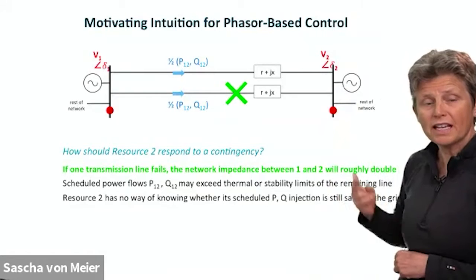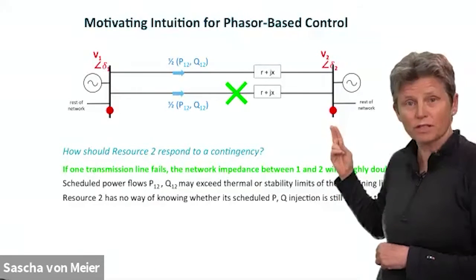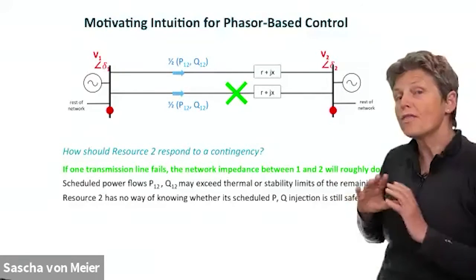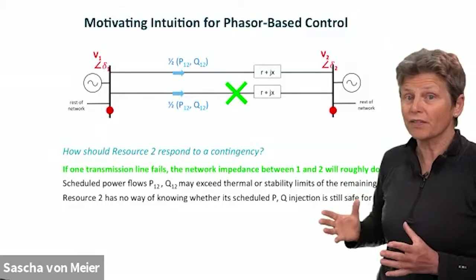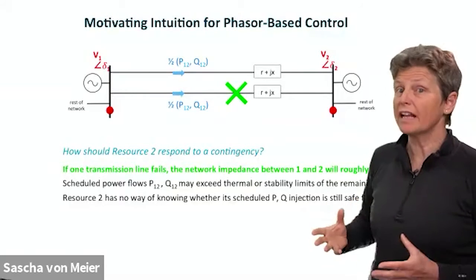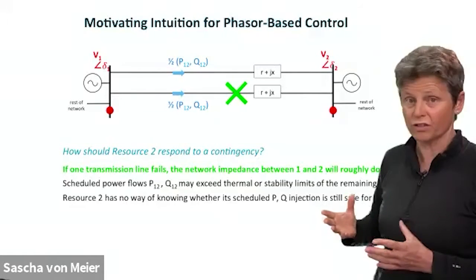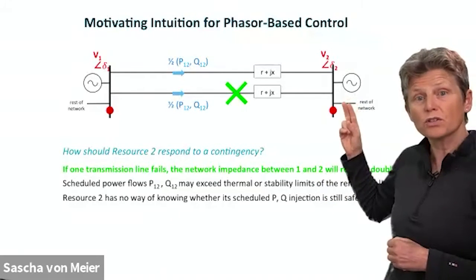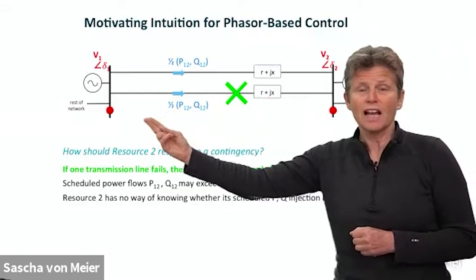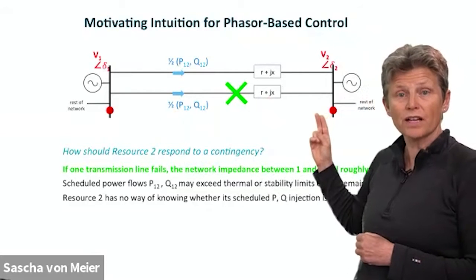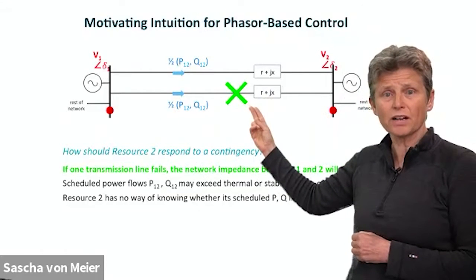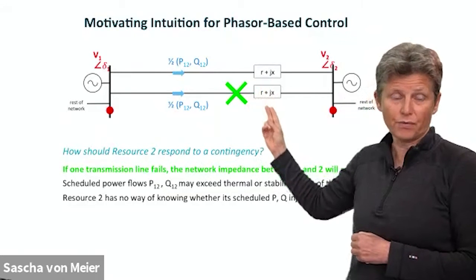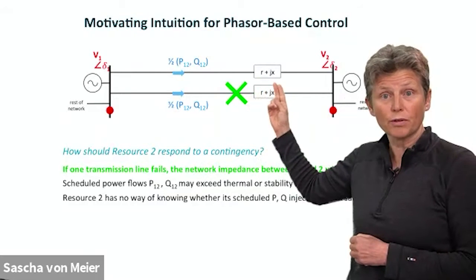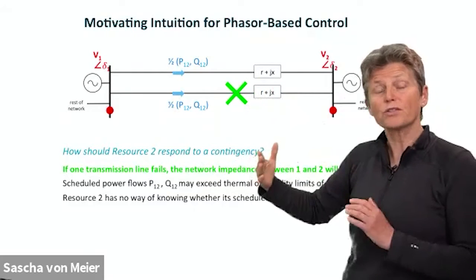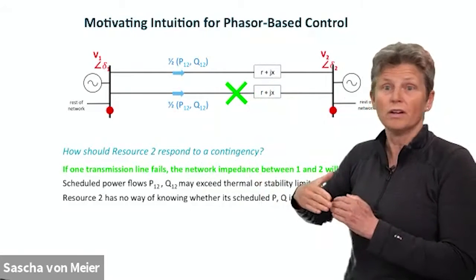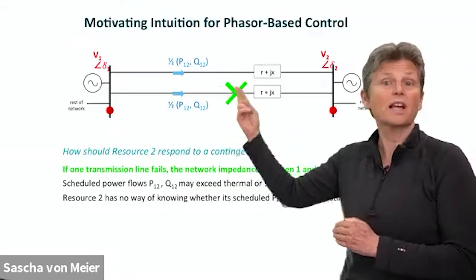What we're proposing here is that by directly measuring the phasor, without needing any information about the nature of the contingency or what just changed, this resource will be able to observe a sudden change in the phasor difference. As this transmission line goes out, if those were the same, the impedance now doubles, and so the phasor difference is going to roughly double for the same power flow.